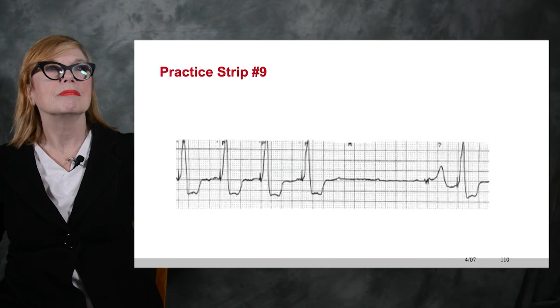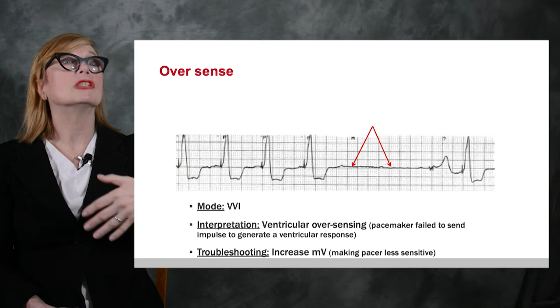That's a ventricular pacemaker that has oversensed. It sensed the P waves and saw that activity as a ventricular beat. That pacemaker is way too sensitive. He cries at every sad movie. Your P wave got sensed by the pacemaker as a ventricular response. So what you have to do is make your pacemaker less sensitive. You're going to increase that millivolt signal. That means that those little bumps that the pacemaker is sensing, their threshold is too low. So I'm going to increase my millivolts so that the little bumps don't get sensed as ventricular beats. We have a failure to fire because we are oversensing the P waves as a ventricular response.